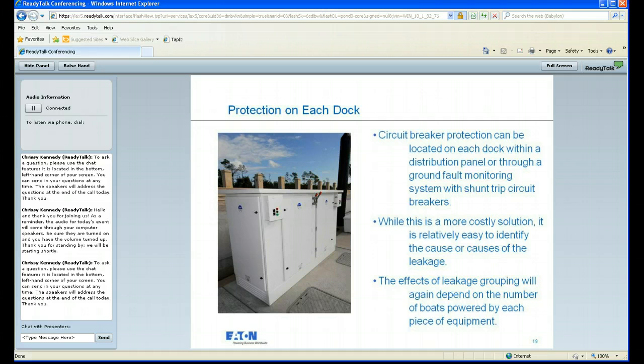You can also provide protection on the dock, whether through distribution panels or substations, transformer panel board combinations out on the dock. You can also provide it through ground fault monitoring with shunt trip circuit breakers. There are some small monitors, which we'll show examples of toward the end of the presentation, that are adjustable and can pick up certain leakage currents and can be supplied with pieces of equipment to turn circuit breakers off. It's a little more economical than just providing GFI circuit breakers throughout the system, and it does meet the intent of that 555.3 code. It's a little bit more costly solution, but it makes it relatively easy to identify the cause or causes of the leakage.